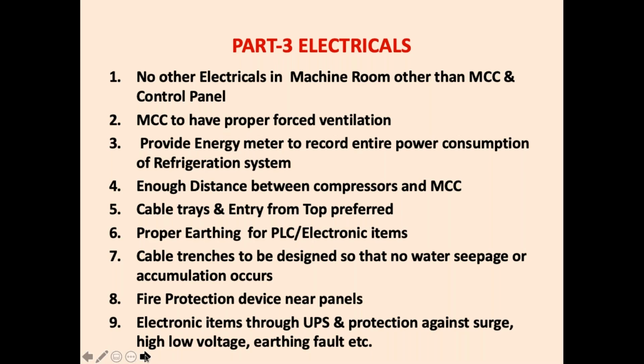MCC should have proper forced ventilation. MCC gets very heated because there are all the contactors and all the terminals inside, so the MCC should have ventilation. Otherwise, there will be overheating and it can catch fire.